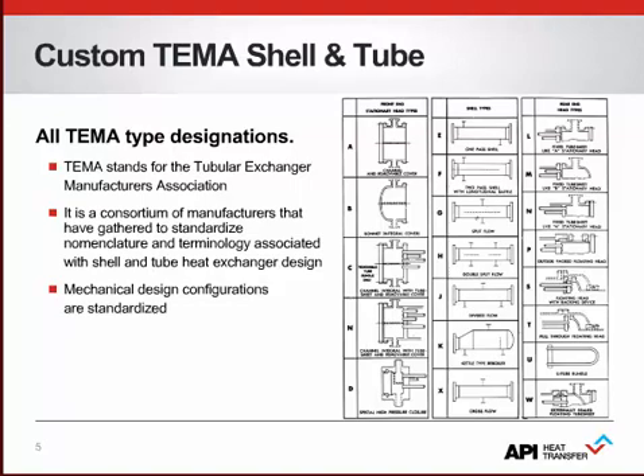Mechanical standards are divided into three classes: TEMA Class C for general service, Class B for chemical process service, and Class R for petroleum service. So when you specify a specific TEMA type and class, you can be assured of what you are purchasing. You can find more information on TEMA standards if you'd like by visiting www.tema.org.